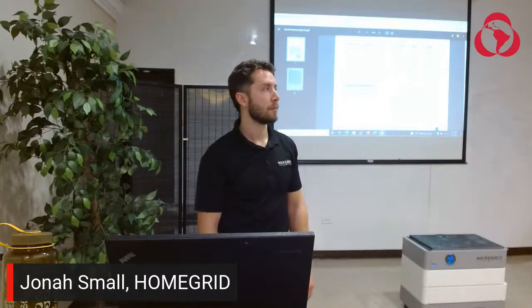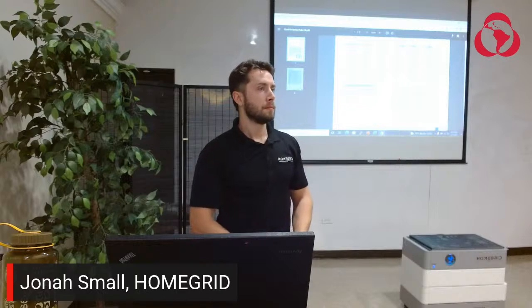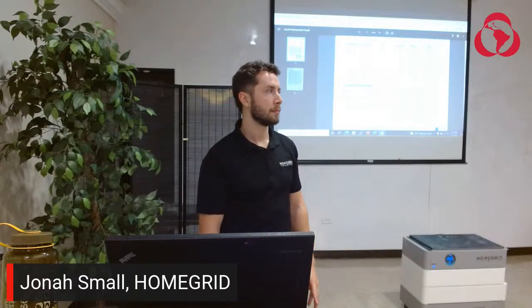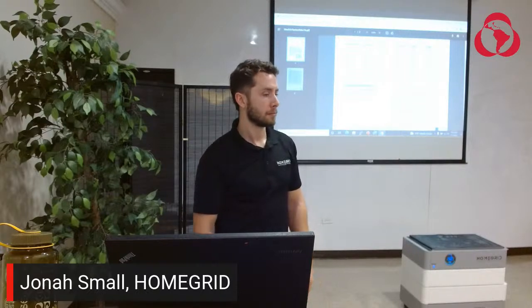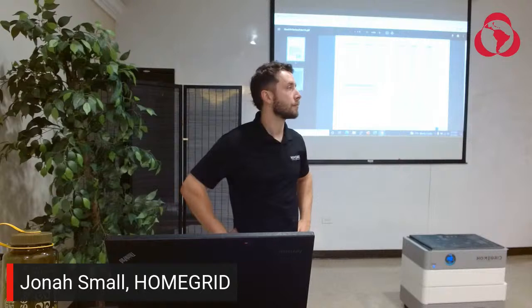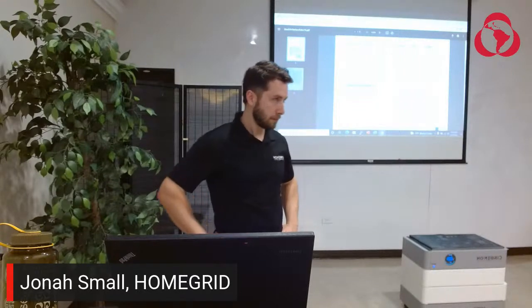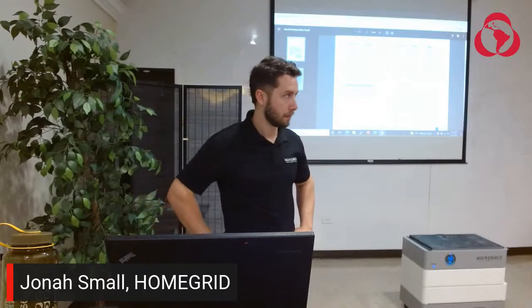You have to understand that it has a lot to do with the consumption of the property. If you're consuming 30 kilowatts, or 15 kilowatts, and you put in a 5 kilowatt generator, and the batteries are drained, the generator is going to turn on, but it's not going to have enough capacity to power the property and charge the battery. So there has to be a balance.